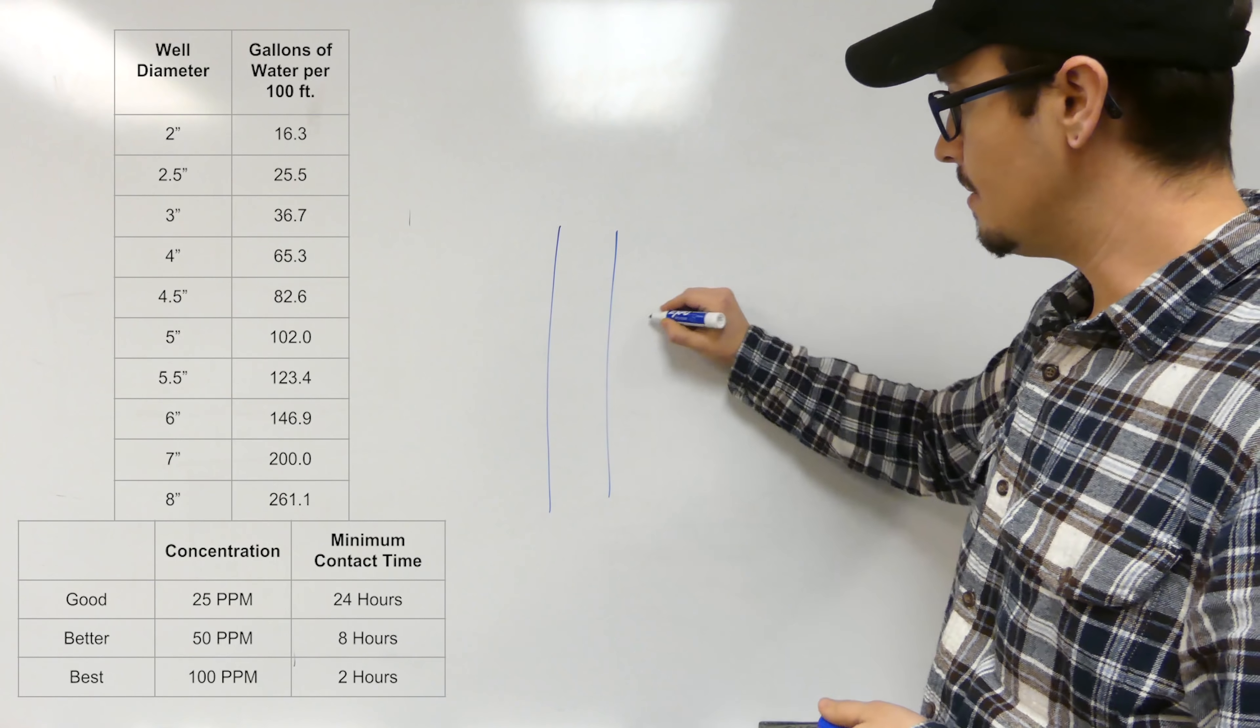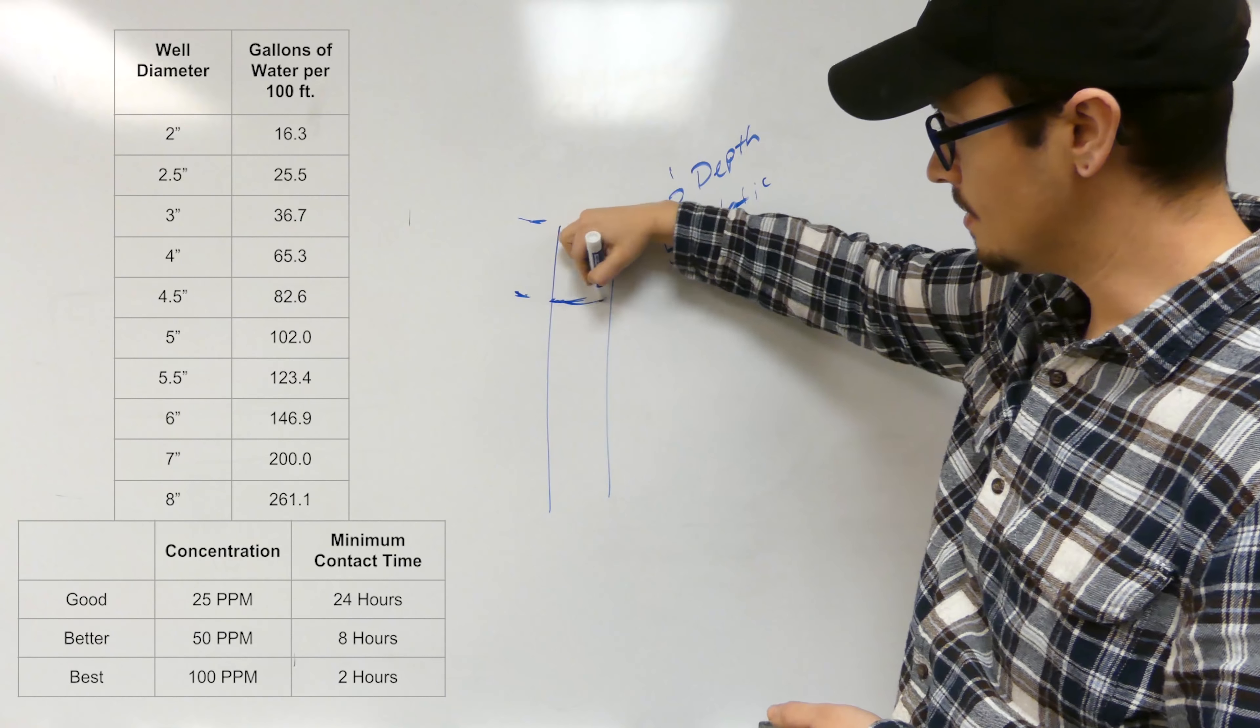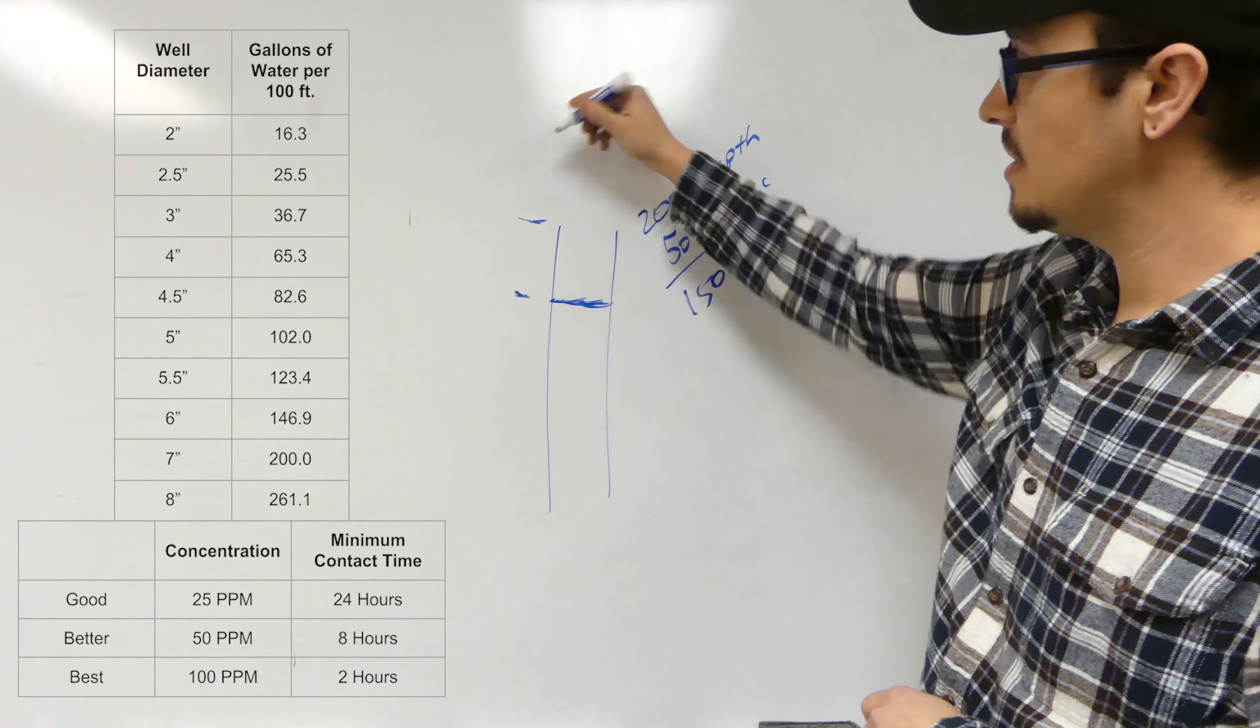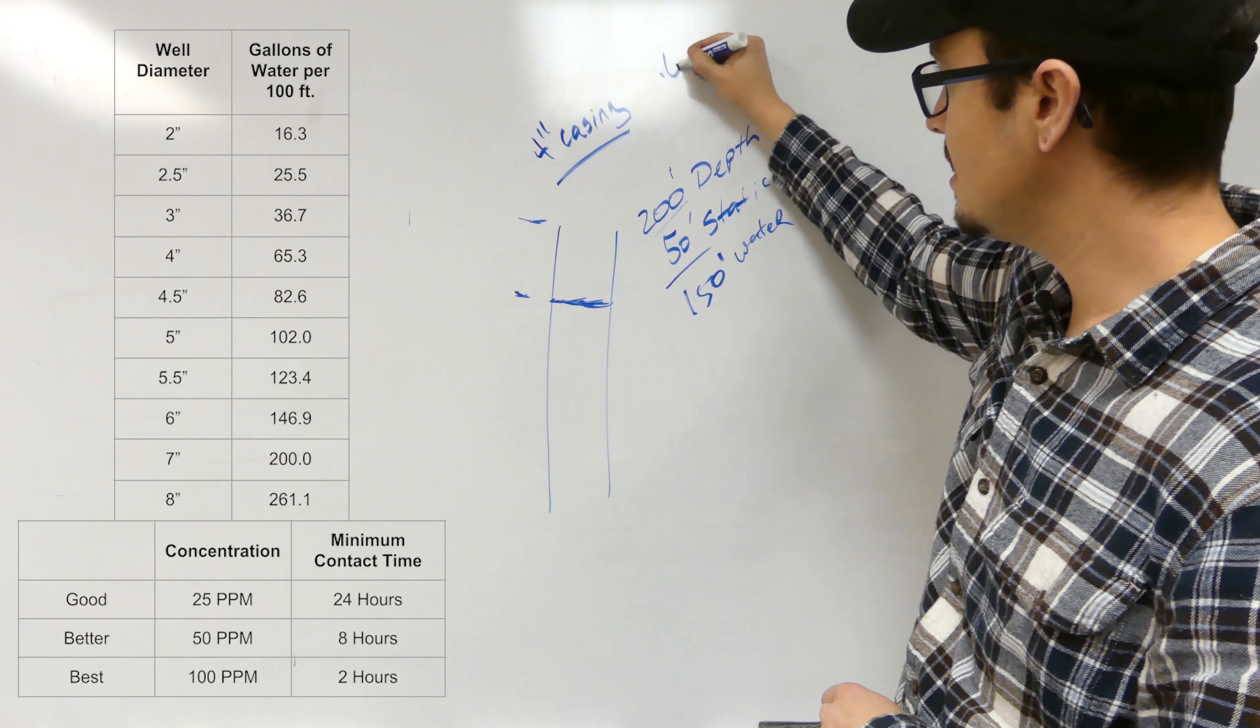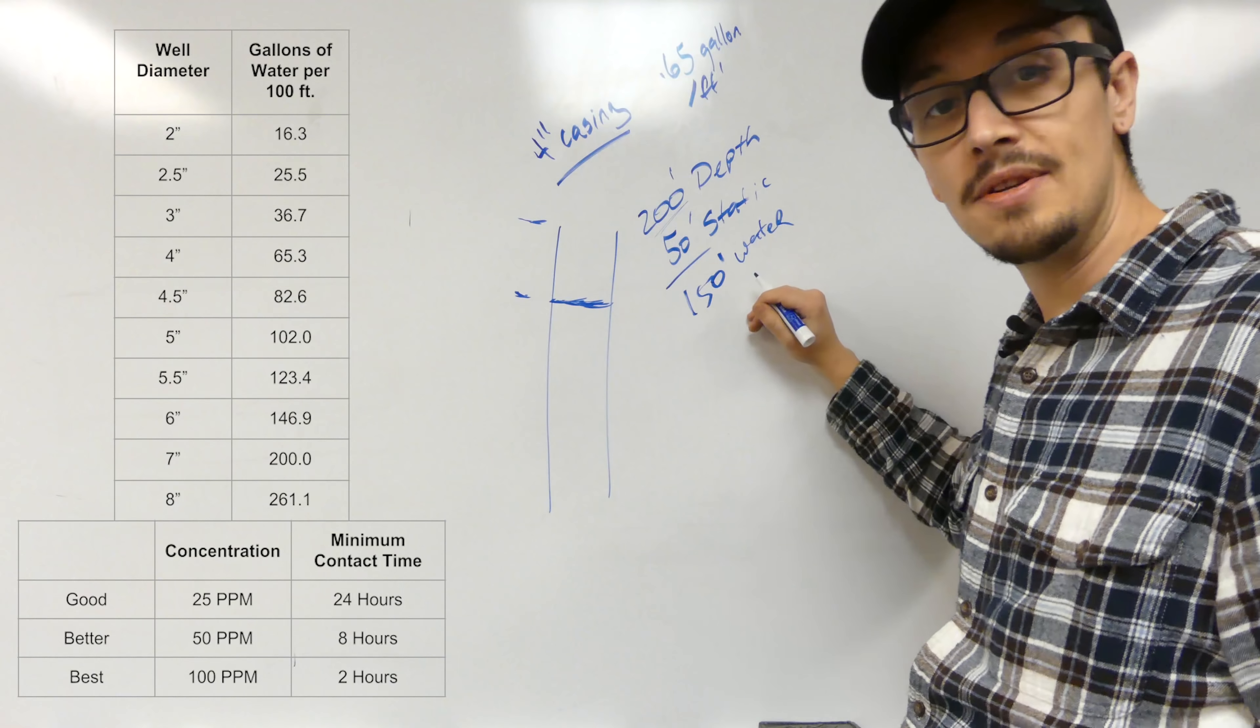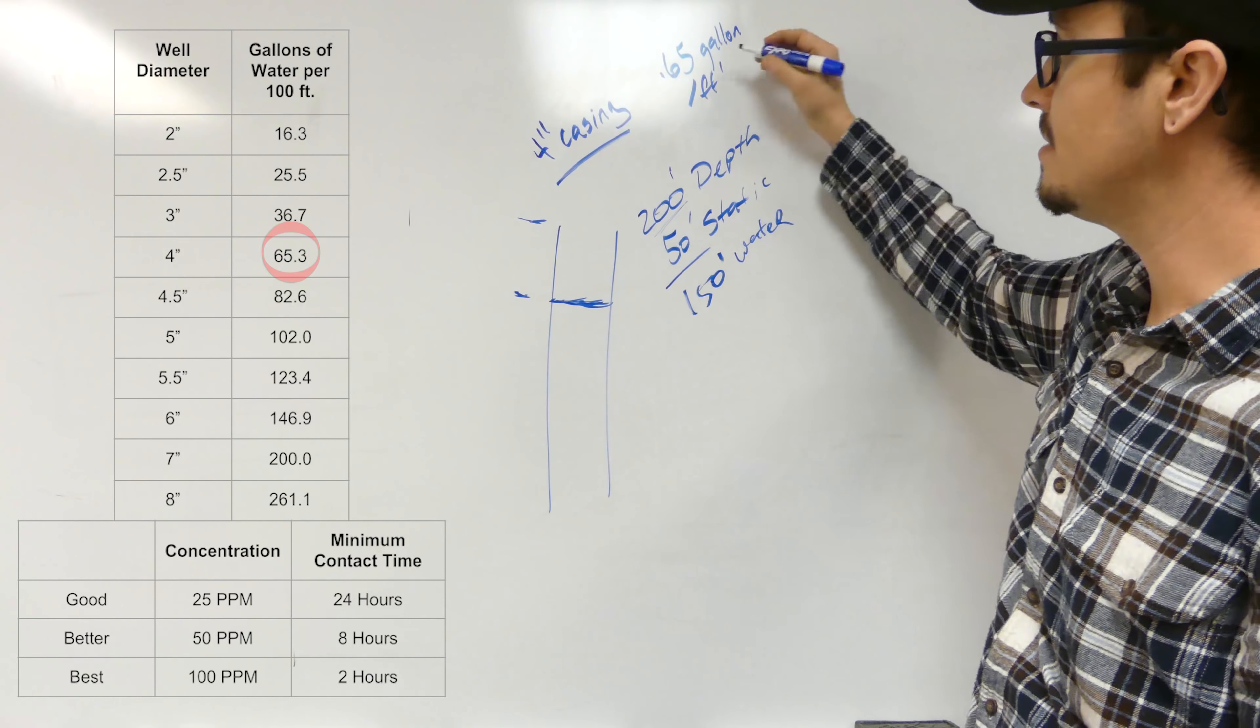Let's jump right into calculating it, just so you get an example. Let's say we've got a well here and it's 200 feet deep. We have 50 foot of static, which is the distance from the top of the well until we hit water. We know we've got 200 minus 50, we've got 150 feet of water. For the sake of easy math, this is a 4 inch casing. A 4 inch casing holds 0.65 gallons per foot. We just simply take 0.65, multiply that by 150, and then we're going to know exactly how many gallons we've got in the well. We want to factor the entire depth of the well, not just the pump depth. We're doing the whole thing.